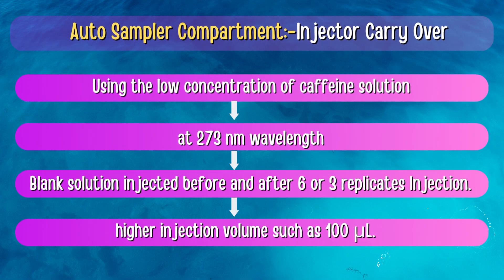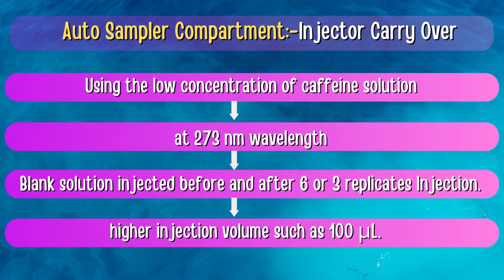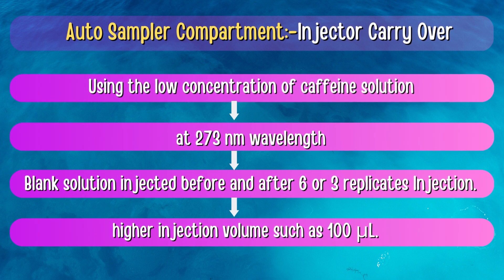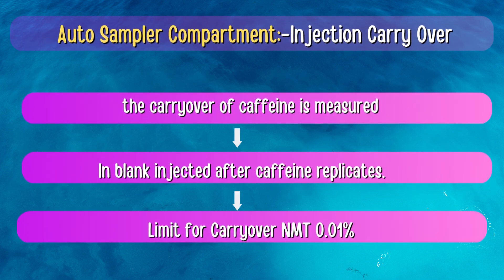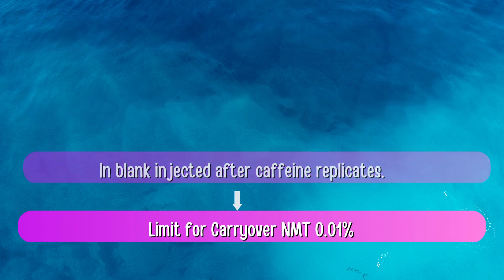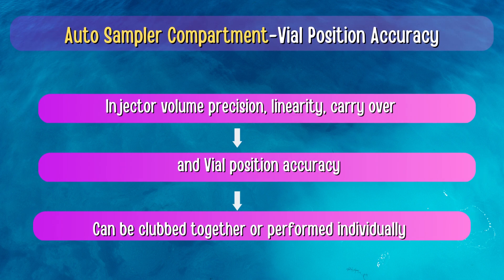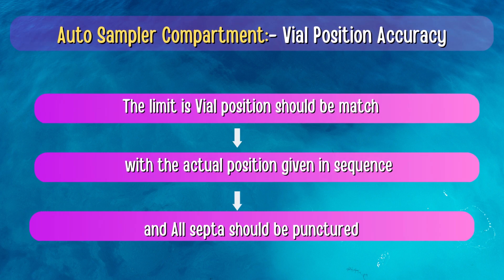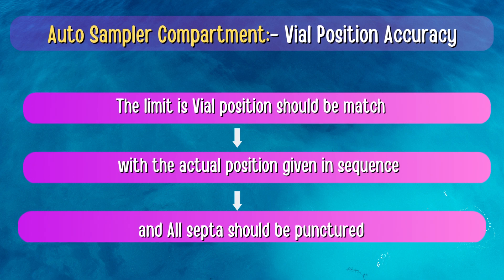For Injector Carryover, a known low concentration of caffeine standard solution at 273 nm is used. A blank solution is injected before and after 6 or 3 replicate injections at higher injection volume such as 100 µL. The carryover of caffeine is measured in the blank injected after caffeine replicates. The limit for carryover should not be more than 0.01%. Injector Volume Precision, Linearity, Carryover, and Vial Position Accuracy can be clubbed together or performed individually. The limit for Vial Position is that the position should match the actual position given in the sequence and all septa should be punctured.